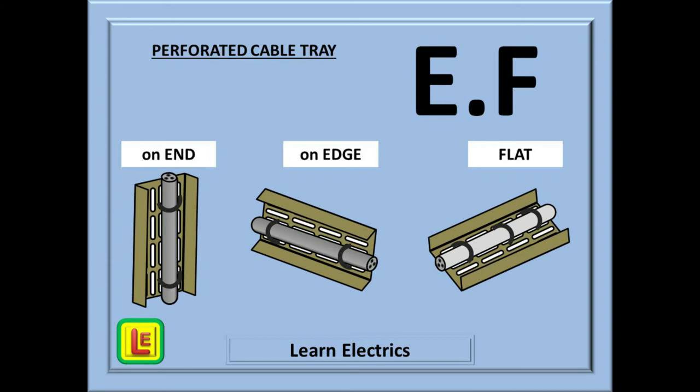E. Moving on to perforated cable trays now. The perforated cable tray can be installed vertically on its end, or it can be installed horizontally on its edge. On its end. On its edge. End and edge both begin with the letter E. Guess what the reference method is? E.